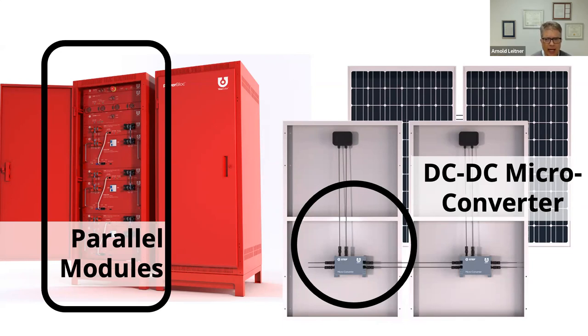It's kind of the same in that you step up the electric potential of the panel, but microinverters step it up to alternating current, while DC-DC microconverters step it up to direct current. That's also not the same as optimizers such as SolarEdge or others. This steps up exactly to the high operating potential of the system, about 380 volts, and makes every panel entirely independent of each other.